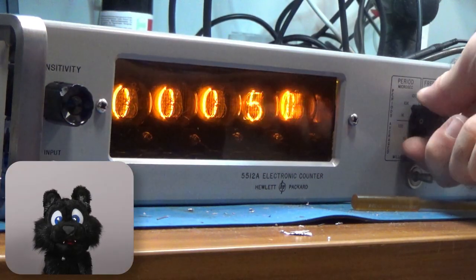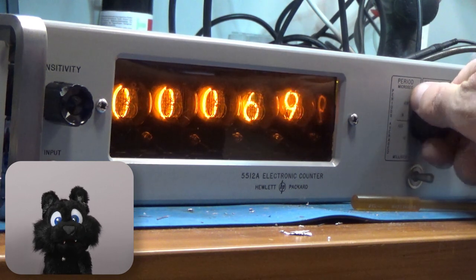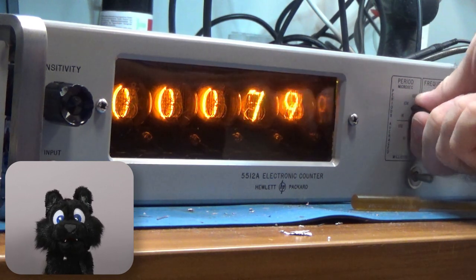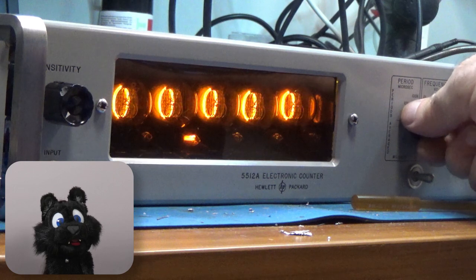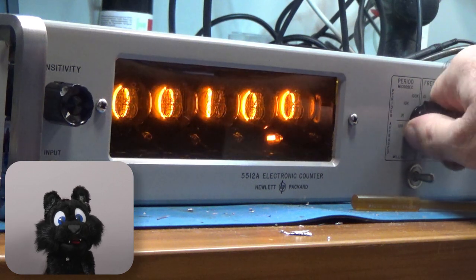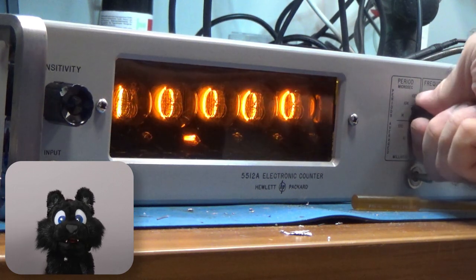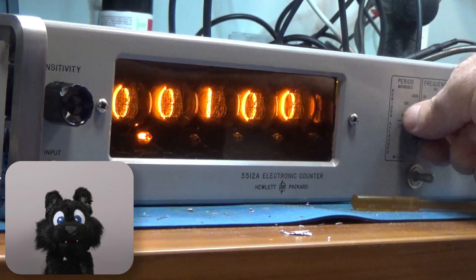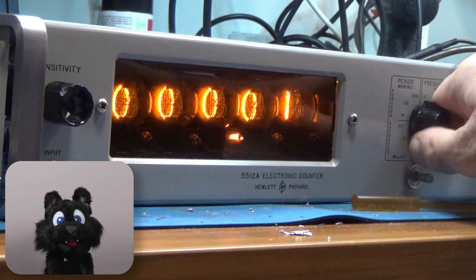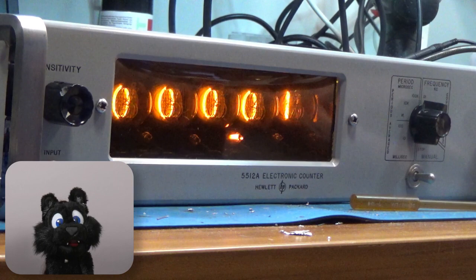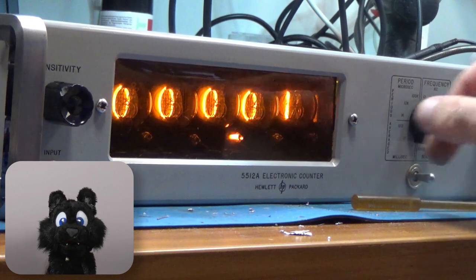Up next is a quick function check. The input sensitivity dial has a latched position for testing. This will put the internal clock to the input, so the display should read all zeros and a single one, except in the two fastest ranges. The counter mode will count in 10 Hz too.